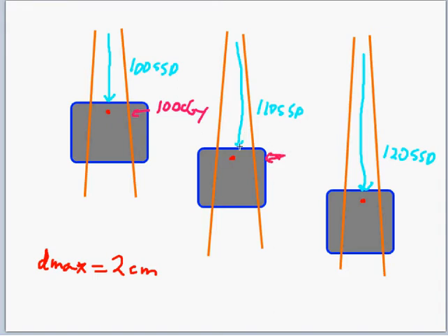Well, if we again use inverse square, the first thing we have to do is figure out the relative distances to the source for these two points. So the question is, how far away is this point from the source? A lot of people jump the gun and make the mistake of saying, well, that's easy, it's just 100 over 110. That's not exactly right, because it's 100 to the surface, and then we're going to go an extra 2 centimeters down to Dmax.